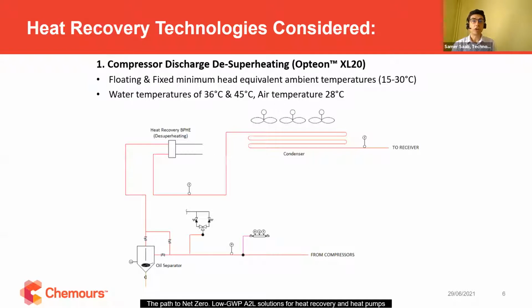Now, if you want to consider heat recovery technologies for a supermarket, we have different possibilities. And we have considered three technologies here. The first one would be the compressor discharge desuperheating. This technology can only be used with Opteon XL20. So in a couple of words, you will see here a schema of the refrigeration system, or one part of the refrigeration system, refrigerant coming out of the compressor, high temperature, high pressure. After the oil separator, we will be having the refrigerant flowing through a brazed plate heat exchanger, where the energy will be recovered for heating and going through a water glycol system, performing the heating in different radiators within the supermarket. It will be here, in this case, in series before the condenser, and that's why we have this technology, in this case, the desuperheating at the compressor outlet.